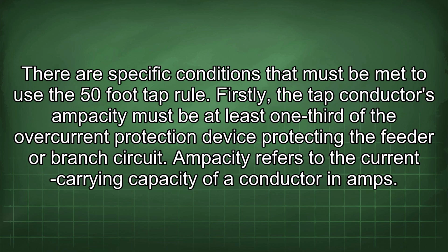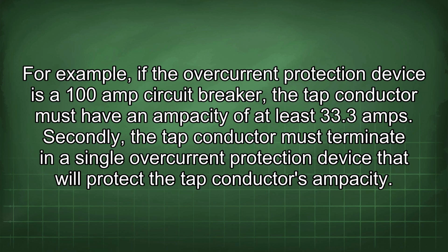There are specific conditions that must be met to use the 50-foot tap rule. Firstly, the tap conductor's ampacity must be at least 1/3 of the overcurrent protection device protecting the feeder or branch circuit. Ampacity refers to the current carrying capacity of a conductor in amps. For example, if the overcurrent protection device is a 100 amp circuit breaker, the tap conductor must have an ampacity of at least 33.3 amps.